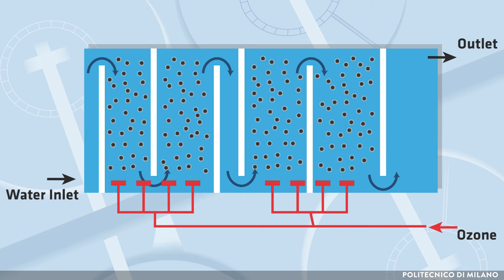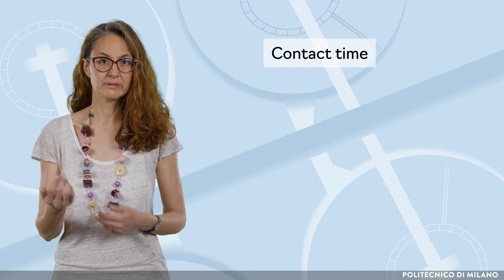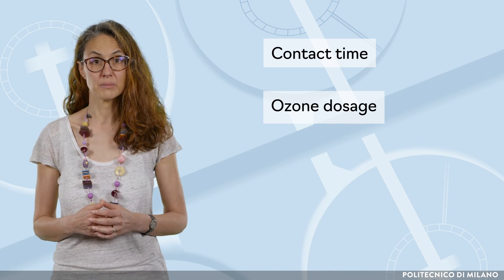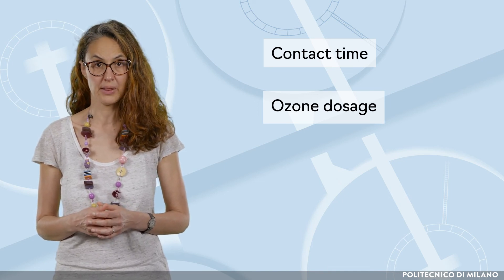In addition, when the oxidizable organic load is high, it is advisable to divide the contactor into two compartments. More recently, different configurations have been introduced, such as pipe contactors or serpentine basins, displaying better hydrodynamics. It is important to evaluate the need for off-gas treatment in case the residual ozone concentration exceeds acceptable levels. As for adsorption, the ozonation main operating parameters controlling CACs removal efficiency are contact time and ozone dosage, having in mind ozone consumption inside oxidation reactions of the effluent organic matter. Even in this case, lab and pilot tests are fundamental to evaluate the applicability of the process.